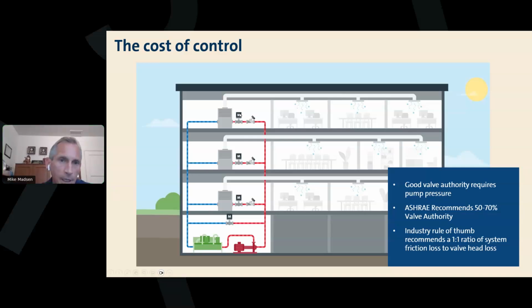Something to keep in mind, that's 50% of the head with this valve in its fully open position. We already know we spend very little time with the valve fully open. We spend a lot of time with the valve under part load conditions. So these control valves are making up more than 50% of the total head in your system. So you can start to see that if we eliminate that head, we can pick up big energy savings.